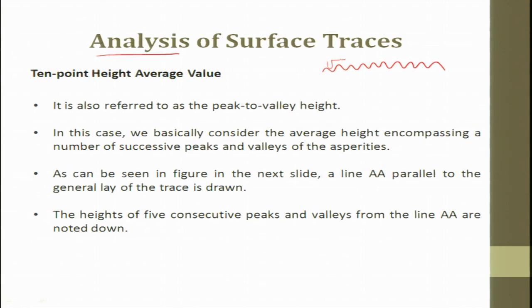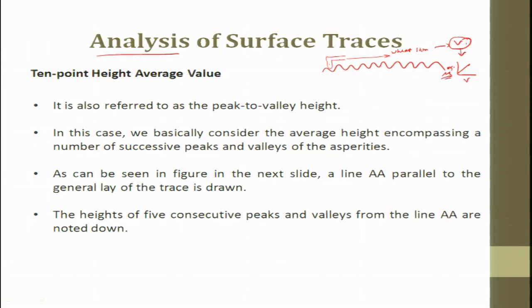You can have a mechanical or electrical approach to measuring roughness. Generally, a stylus is attached to a Wheatstone bridge principle circuit. The output is calibrated and we get a voltage that corresponds to the magnitude in microns. The physical data is converted into voltage, calibrated, and displayed as microns — this is an example of the transducer principle discussed in previous lectures.